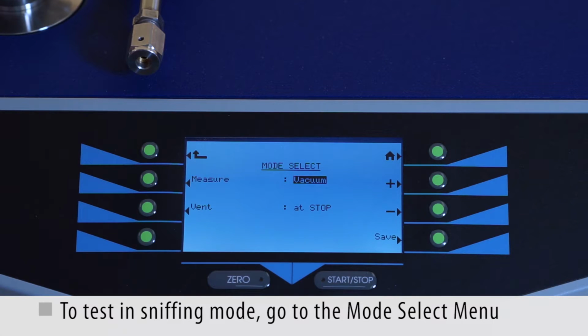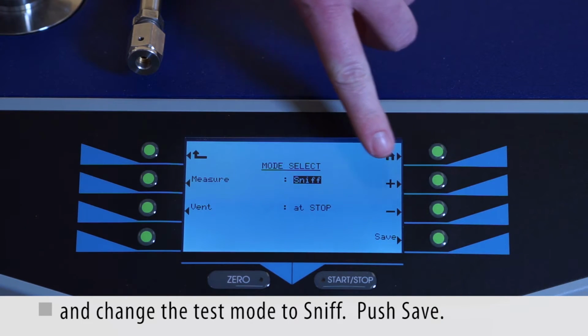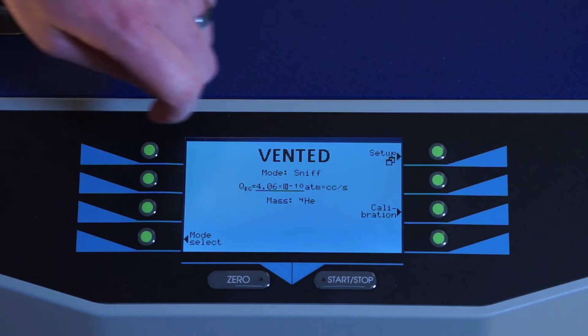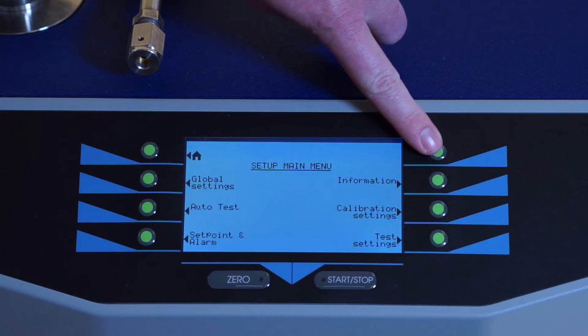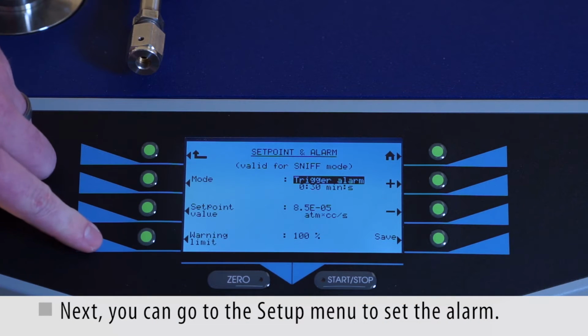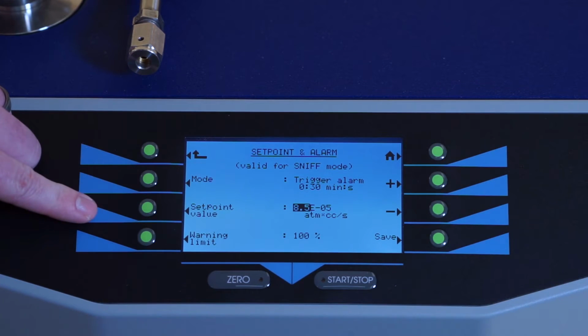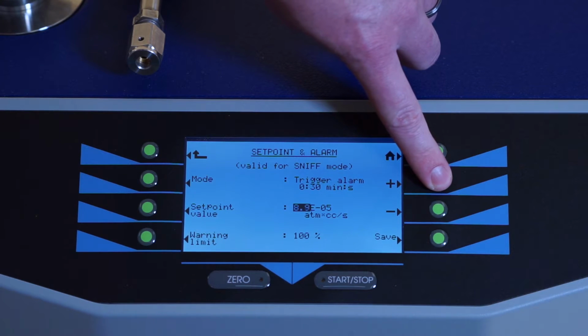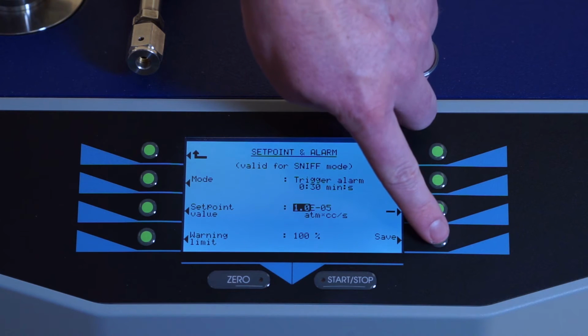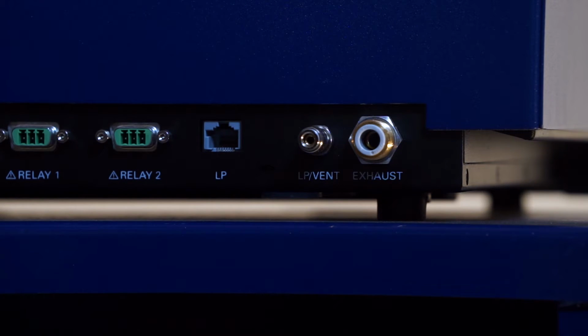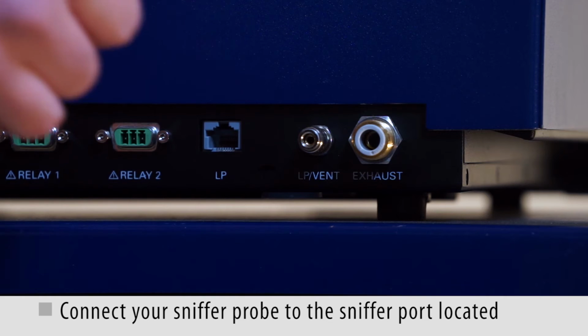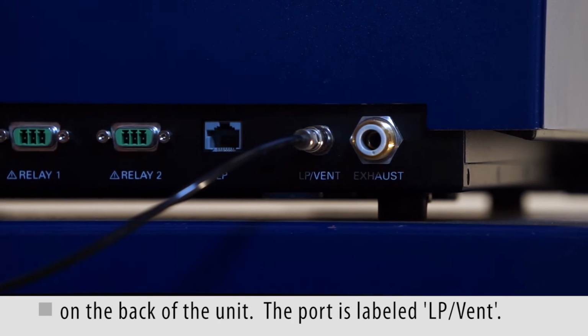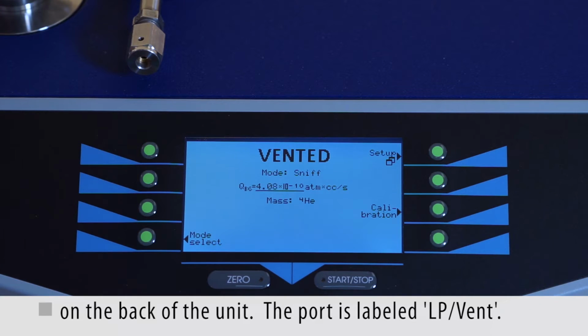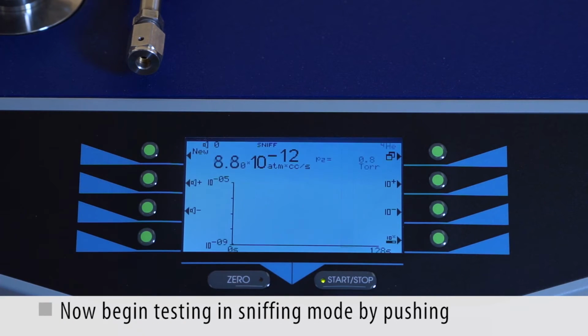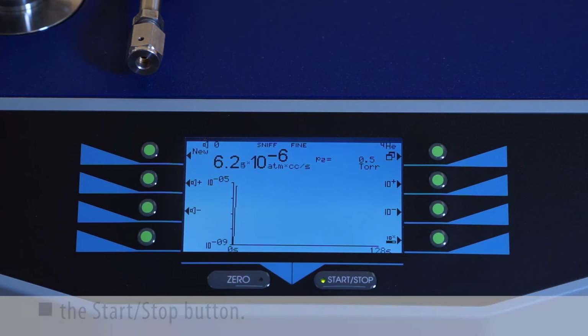To test in sniffing mode, go to the Mode Select menu and change the test mode to sniff. Push Save. Next, you can go to the Setup menu to set the alarm. Connect your sniffer probe to the sniffer port located on the back of the unit. The port is the one labeled LP Vent. Now begin testing in sniffing mode by pushing the Start/Stop button.